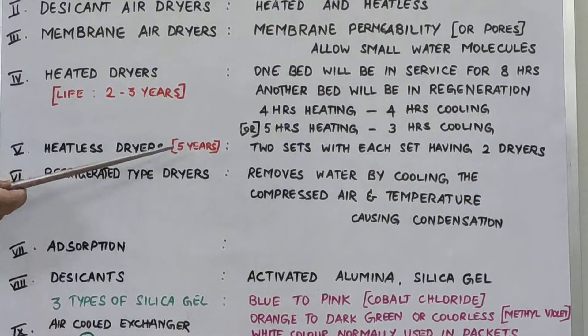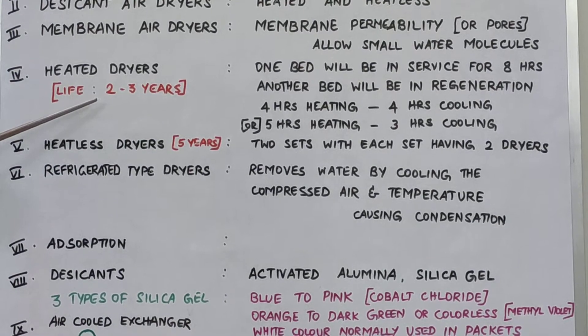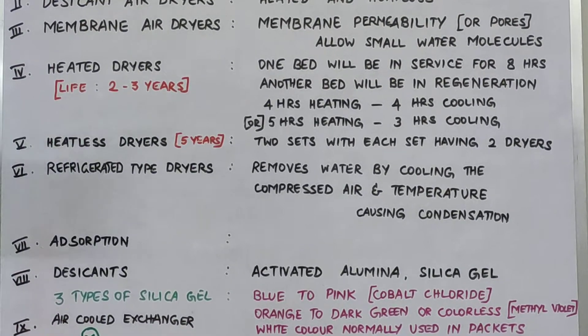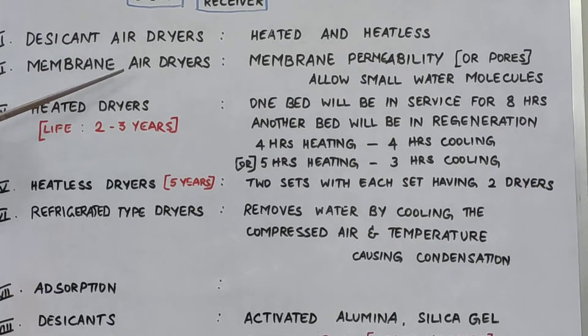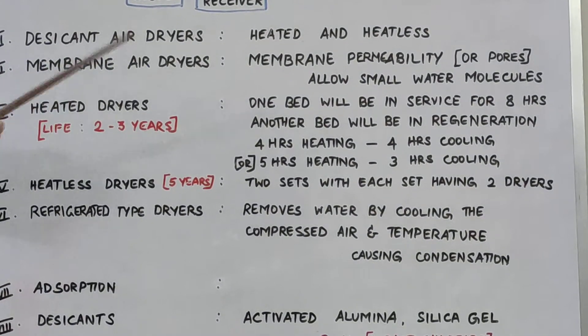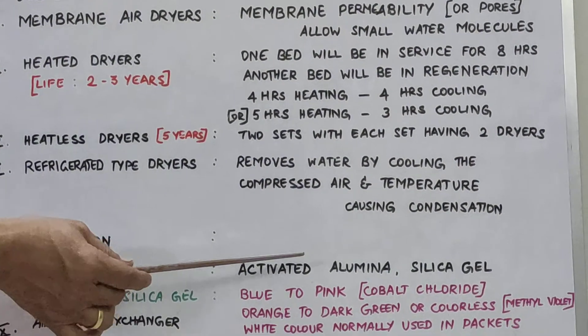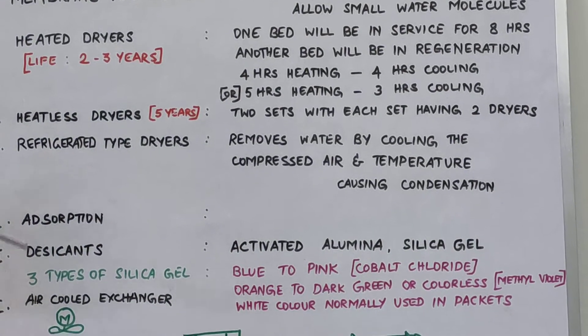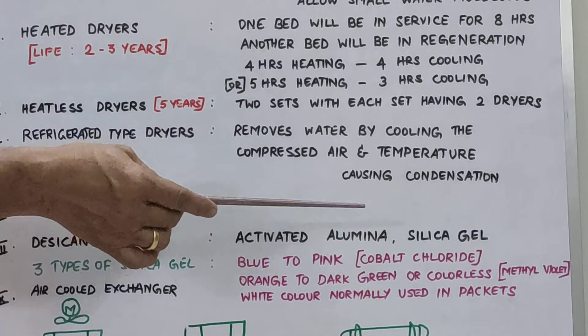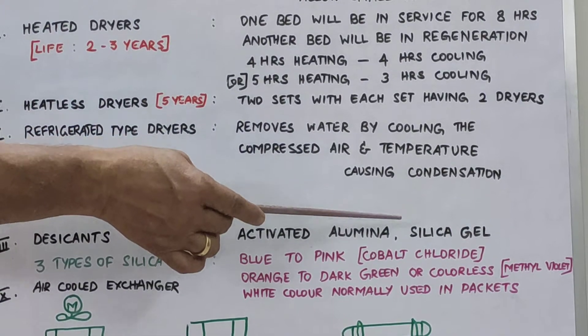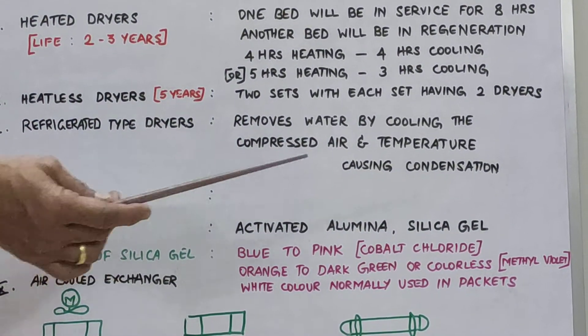The heatless dryer has a desiccant life of approximately five years, while the heated dryer desiccant life is normally two to three years. The desiccant used to remove moisture is of two types: activated alumina and silica gel. Activated alumina is also used alongside silica gel, and silica gel is used in sight glasses to indicate moisture abnormalities.